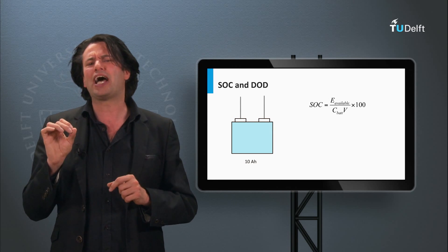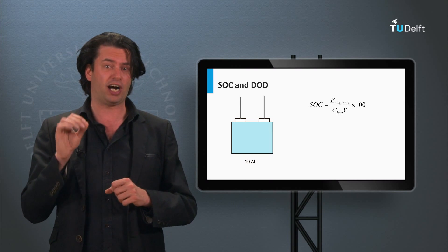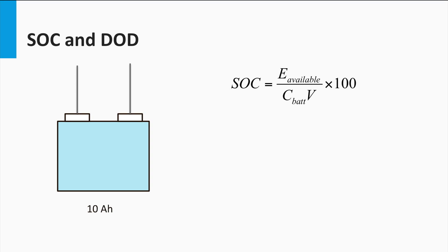Now let's look at another important battery parameter, the state of charge or SOC. This is defined as the percentage of the battery capacity available for discharge. This 10 Ah rated battery that has been drained by 2 Ah is said to have a state of charge of 80%.